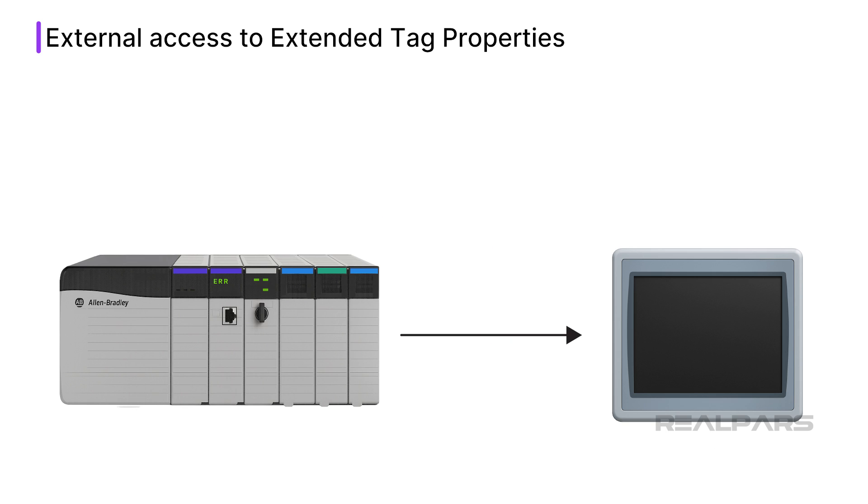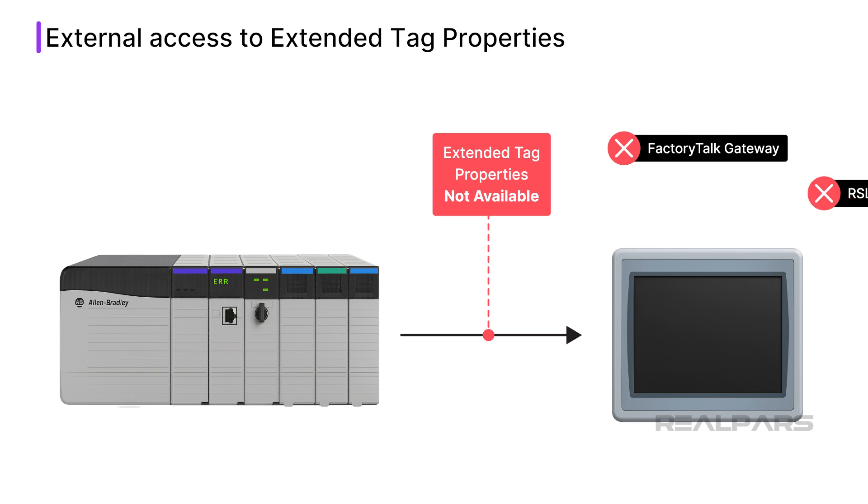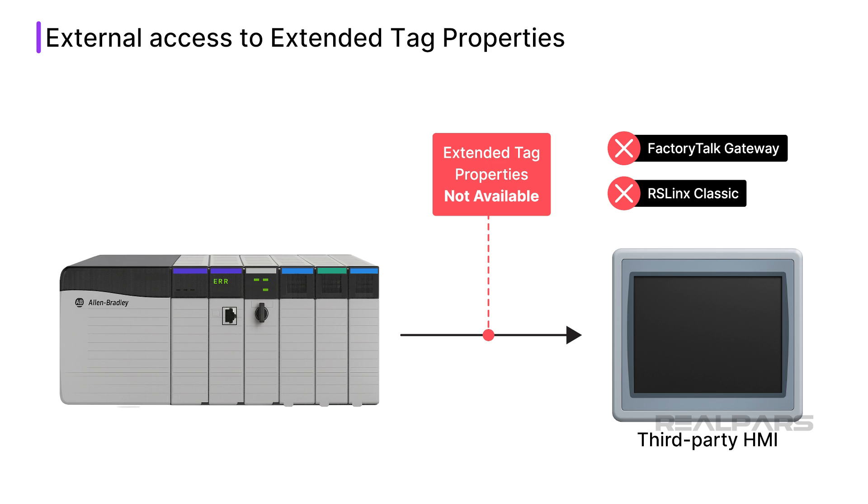Since Extended Tag Properties are not exposed via FactoryTalk Gateway or RSLinx Classic, they cannot be accessed by third-party HMI products.